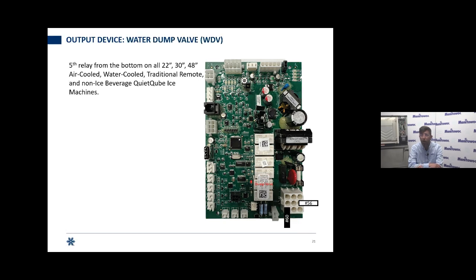All right, but the water dump valve, it's the fifth relay from the bottom. It's going to correspond with wire 60, that black wire, and wire 56, that white wire. So what you're looking for there is power across those two. Keep in mind, the pump is on during water purge and during freeze and during the first 45 seconds of harvest, as we refer to it as the harvest purge. It's the fifth relay from the bottom.